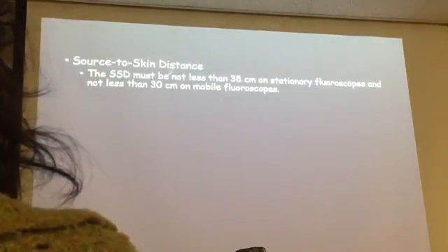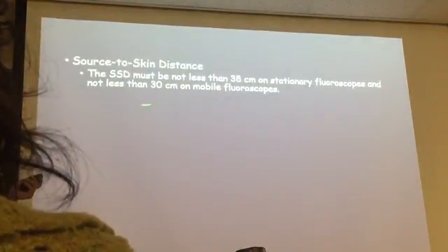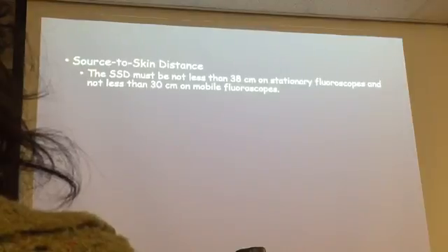That plastic cone is there for a reason, guys. It is to prevent X-ray techs or doctors from getting any closer than 30 centimeters.